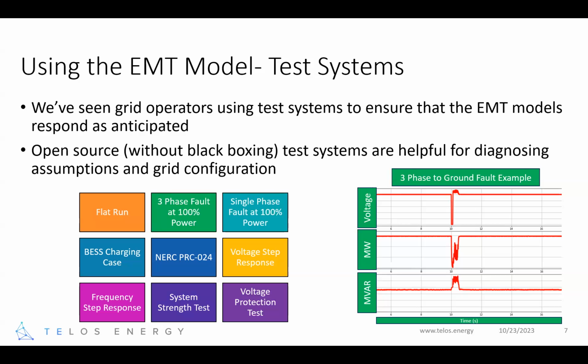When we talk about using the EMT model, we've seen more recently the use of test systems by grid operators, where grid operators during the interconnection process give us a test system, if you will, to represent the grid equivalent and showcase a variety of tests that the PSCAD model is expected to perform to. We'll test the flat run of the model, make sure it initializes correctly, and we'll also test some responses, understanding that this model is PRC 24 compliant, for example, and has the correct protections in place. These test systems are very useful if they're open source or if they come with really good documentation in order to understand the grid equivalents behind them and what type of, for example, short circuit ratio the system is being tested to for the configuration.